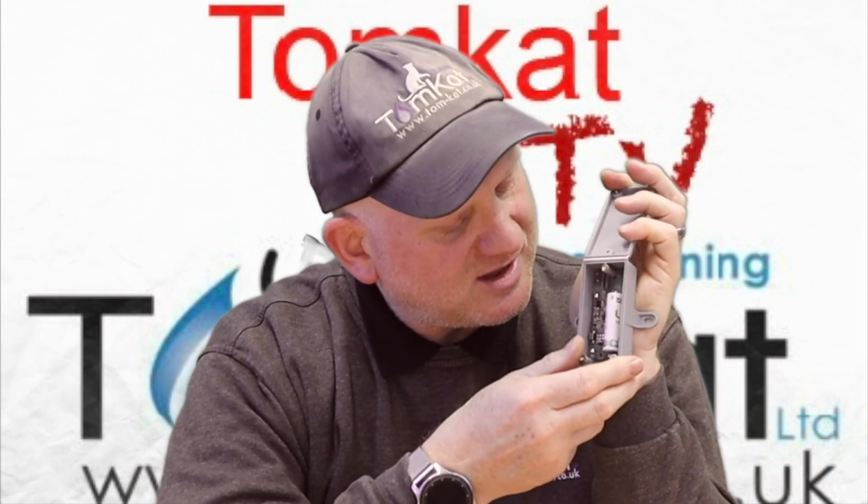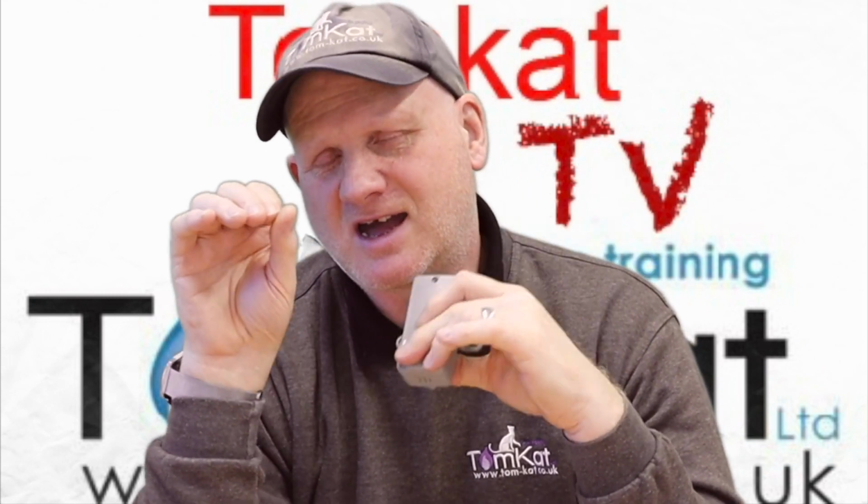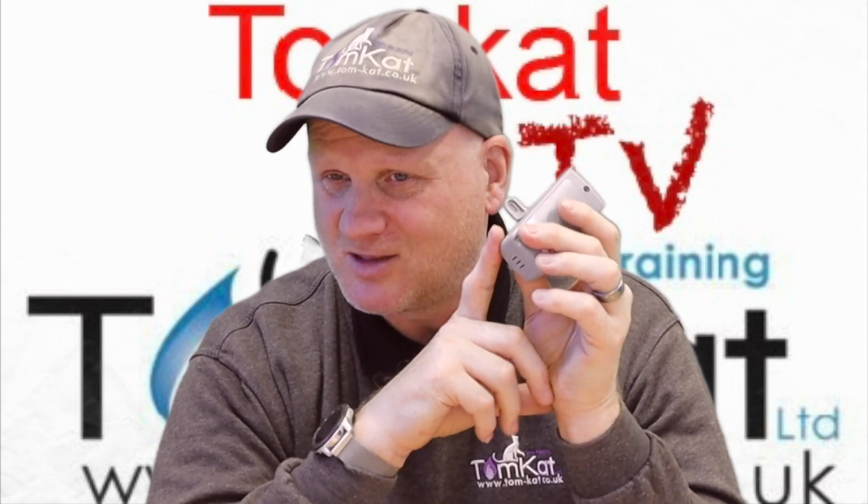So if we do have a look inside this one, all you can see is there's a battery and a little PCB, which is how this sends all the stuff back to the sender receiver. So we've had customers ring us and go, my boiler's not coming on, because spring, summer and autumn time we might get warm days where it's warmer outside than it is inside the house, and people want the heating to come on, but this stops the heating coming on.